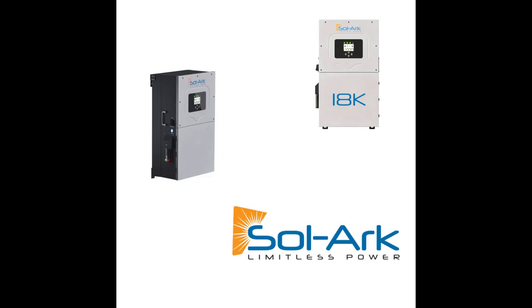Again, you don't need an ATS with the Sol-Ark 18K or 15K when you connect directly to a 200 amp service panel and take the customer off grid. So you're saving $2,000 on an automatic transfer switch. You're saving not only that, but you're saving on the sub panel that it takes to install. So the cost of the sub panel and the labor to move your main loads to a critical load panel from the electrician contracted to do the install. So really, that's some hidden cost savings there that's not even portrayed in this value chart against some of our competition.